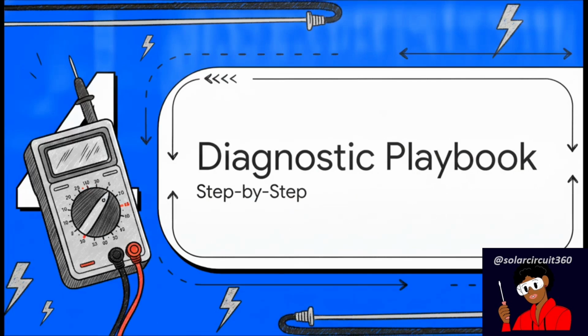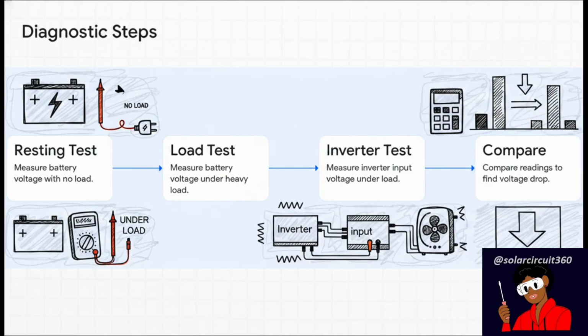All right, Section 4, the diagnostic playbook, step by step. Here is a foolproof, evidence-based process that is going to completely eliminate the guesswork for you. Step 1, measure your battery voltage at the terminals with absolutely no load to get your baseline. Step 2, turn on a heavy appliance and measure that battery voltage again, this time under load. Step 3, keep that load running and move your meter over to measure the inverter input voltage under load. And finally, step 4, compare those last two readings. That's going to calculate exactly how much voltage is dropping across your cables.